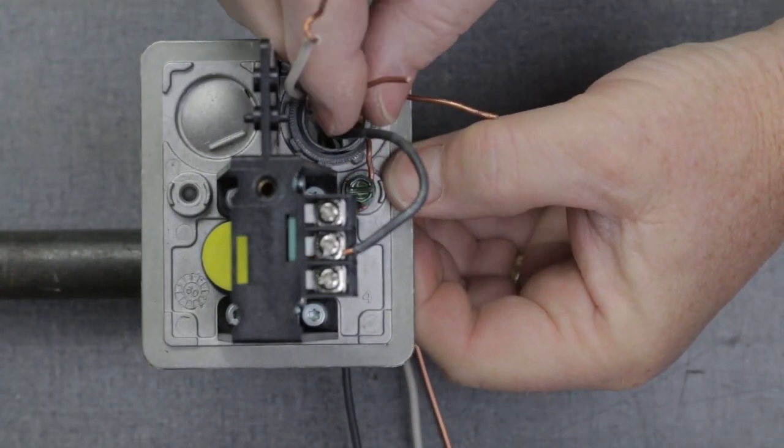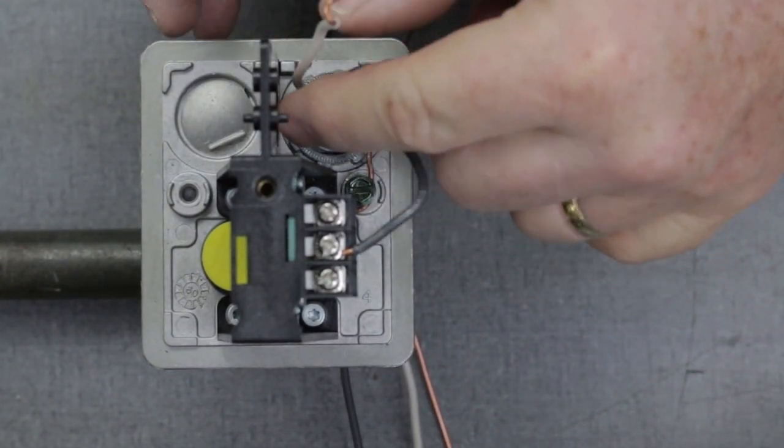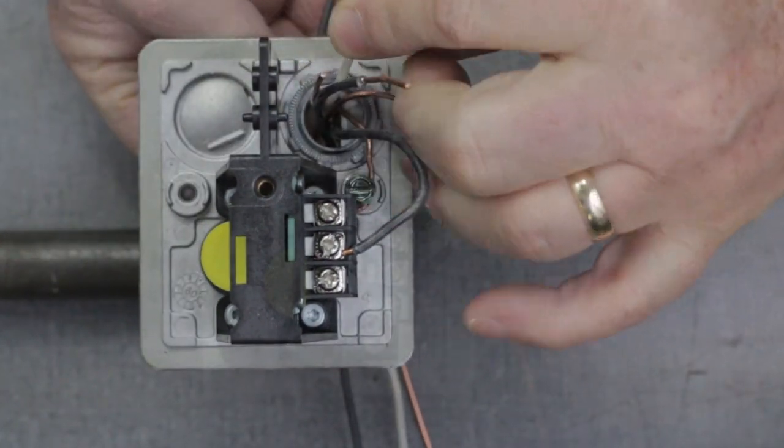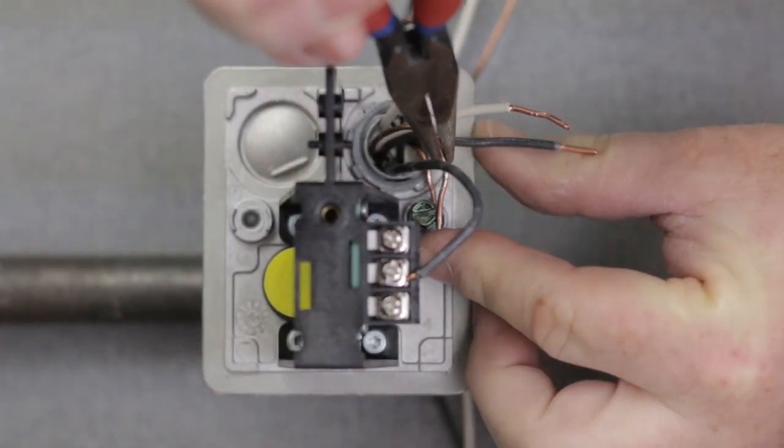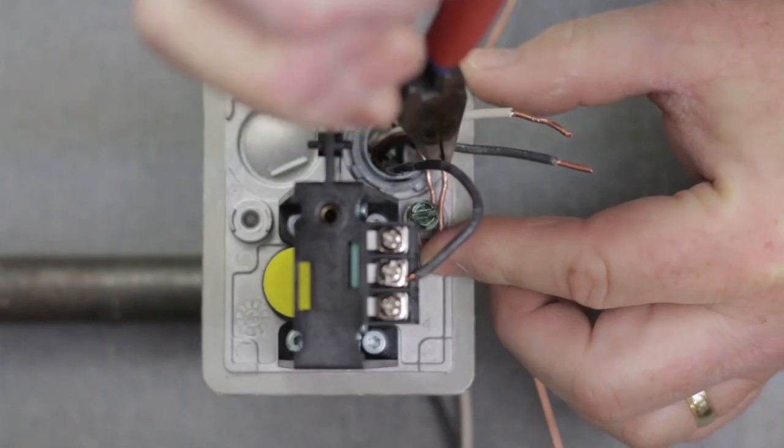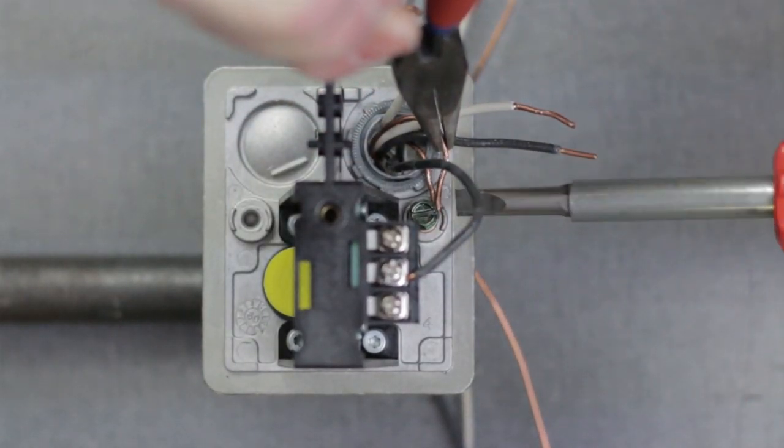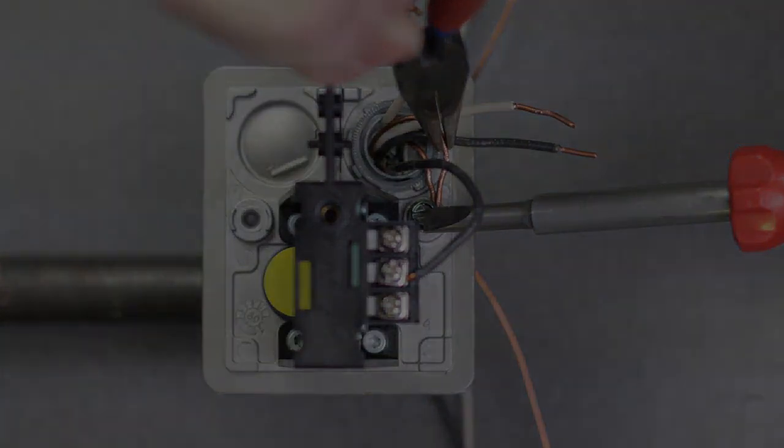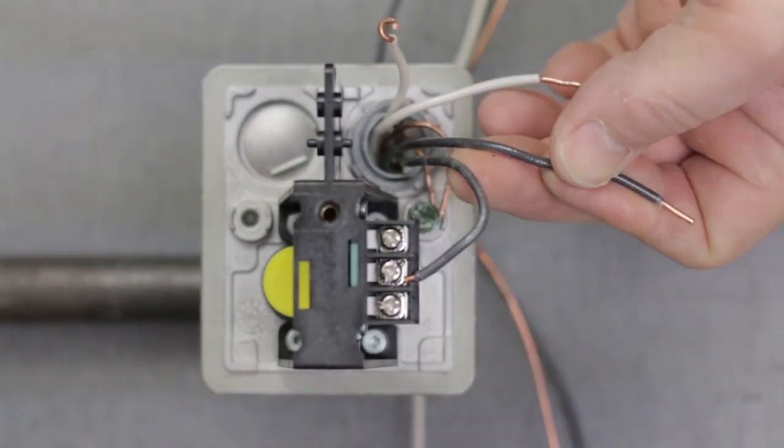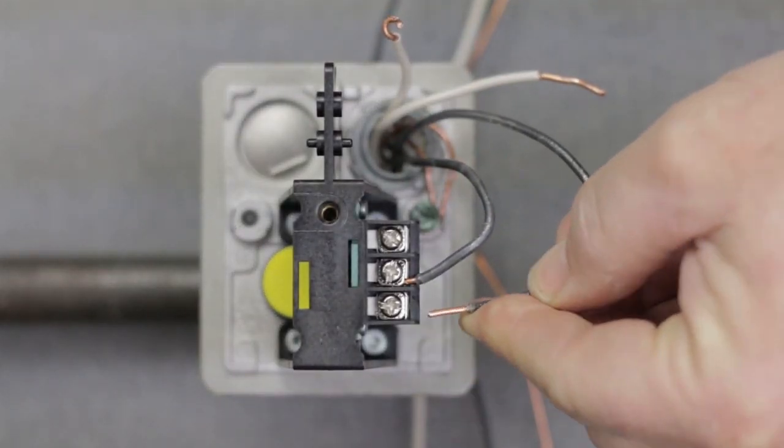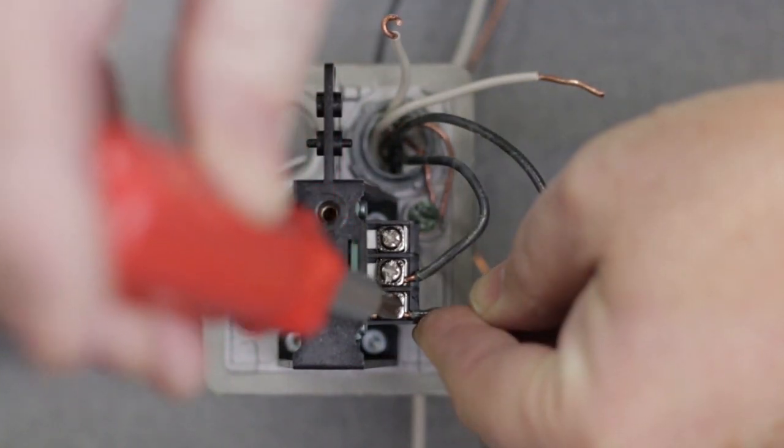Pull another set of wires for the bell into the pressure switch housing. Connect the other ground wire to the ground screw on the pressure switch. Connect the black wire for the bell to the common terminal of the PS10.